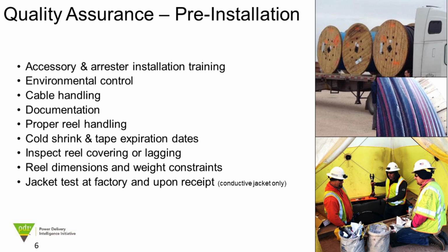I would say, remember that the purpose of testing is to make sure that nothing went wrong, but it is not a cure for a process that was not done properly. One of the things that I found out is particularly for medium voltage, when they directly bury the cable in the ground, if the specifications for directly burying the cable, if the ground is full of rocks and sharp areas, if the compaction is not right, there are rules to do things right. If you follow these rules, then the test just verifies that you didn't have a problem. It doesn't help you much if the test shows that you had a problem and now you have to dig up the cable again. That's not the idea.